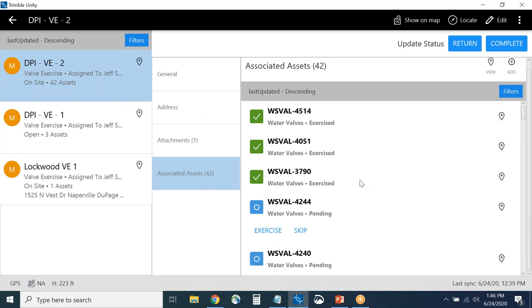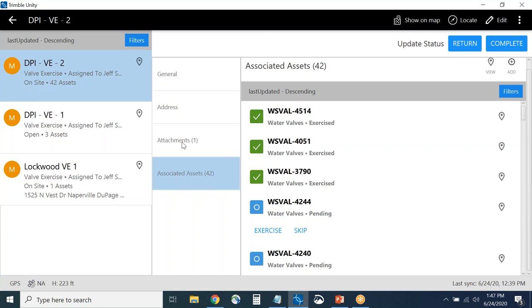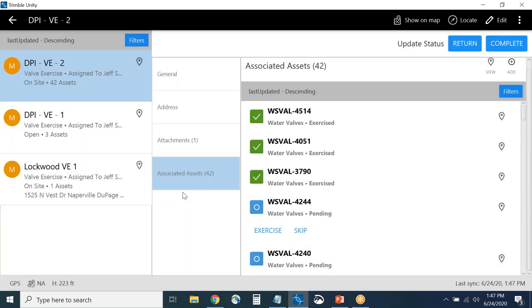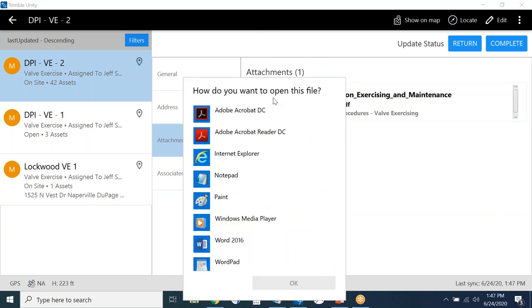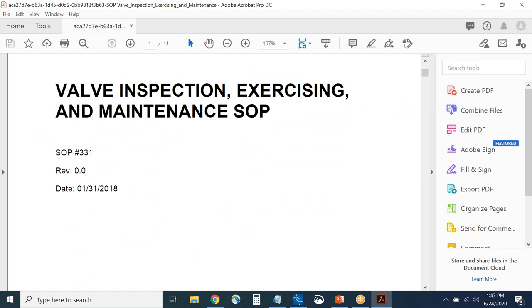As soon as my laptop syncs with the cloud — which can be set to happen every minute, or triggered manually — all of this information becomes visible to the Trimble Unity Web supervisor, who would see all the different valves that have been inspected. I'll trigger the sync now to upload to the cloud. You can set synchronization to happen at a user-defined interval or manually — it only sends what you've done since the last sync, so it's very small packets of data.